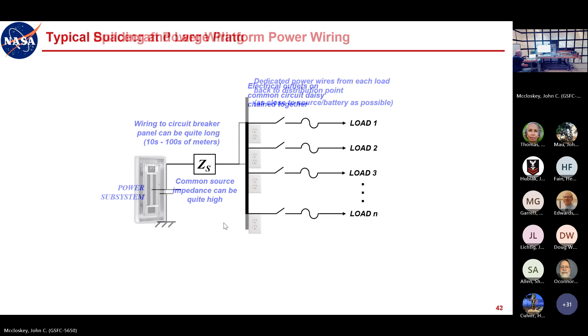Or even think about your house. If you've done any wiring in your own house, the electrical outlets on a common circuit in a room, or even a given group of rooms, are generally daisy chained together. You run one pair of wires up to the nearest outlet, and then daisy chain them together. So their common source impedance can be quite large, since the wiring to the circuit breaker panel can be quite long. In your house maybe it's 10 meters, but in a large building it could be hundreds of meters, so that common source impedance can be quite high.